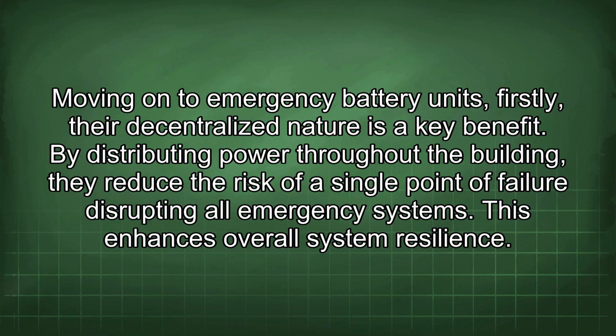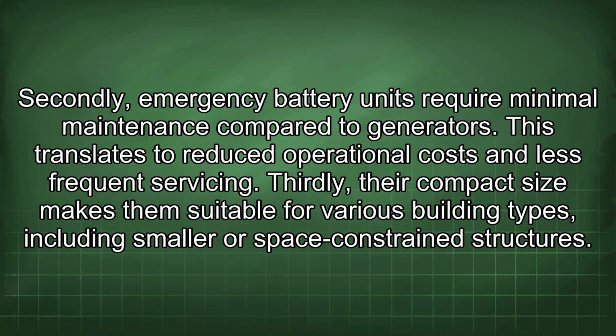Moving on to emergency battery units, firstly, their decentralized nature is a key benefit. By distributing power throughout the building, they reduce the risk of a single point of failure disrupting all emergency systems. This enhances overall system resilience. Secondly, emergency battery units require minimal maintenance compared to generators. This translates to reduced operational costs and less frequent servicing.